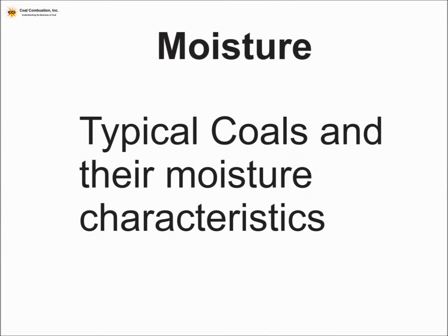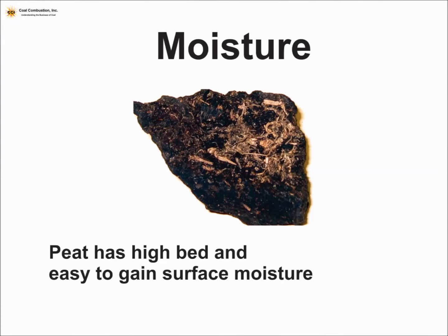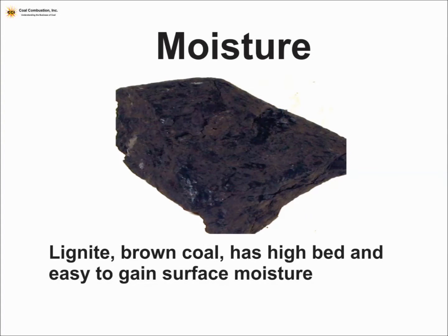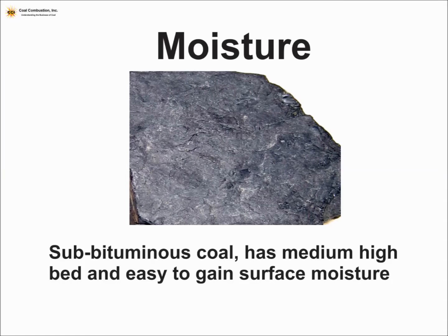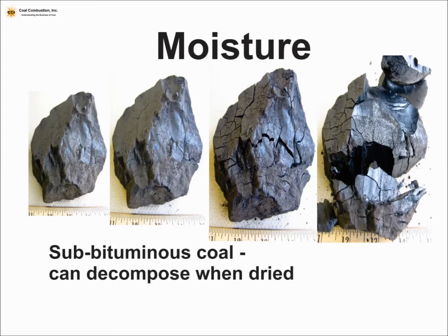Here are some pictures and typical moisture characteristics, looking at that bed or inside moisture versus the propensity or desire for a coal to have high surface moisture. High fine sizes, or a lot of fines, always increases the surface area of the material, so surface moisture has more of an impact, particularly with handling. As we progress through the ranks, there are lower and lower bed moistures. Sub-bituminous coal, unfortunately, when it dries, tends to crack up and create more fines, which again leads to problems with more surface moisture.